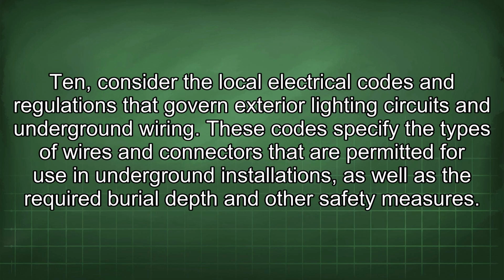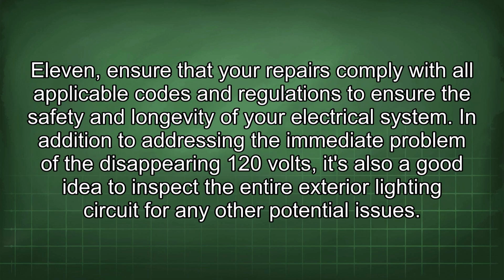10. Consider the local electrical codes and regulations that govern exterior lighting circuits and underground wiring. These codes specify the types of wires and connectors that are permitted for use in underground installations, as well as the required burial depth and other safety measures. 11. Ensure that your repairs comply with all applicable codes and regulations to ensure the safety and longevity of your electrical system. In addition to addressing the immediate problem of the disappearing 120 volts, it's also a good idea to inspect the entire exterior lighting circuit for any other potential issues.